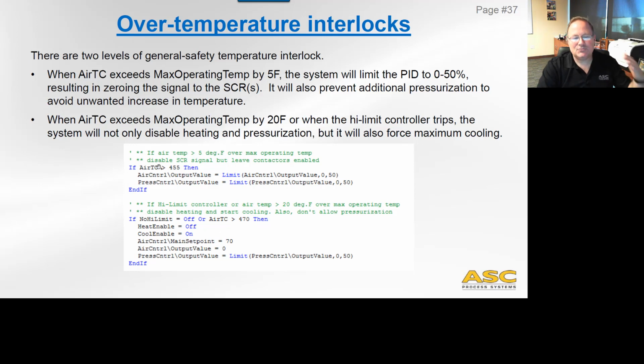And we're taking those two different steps here. One is when the air temperature just goes a little bit above, we're just going to limit air control and pressure control to no more than 50%. What that does is stop heating and stop pressurization, and hopefully that's just a little overshoot that's occurred, and we don't want to take drastic action like dropping contactors and doing this other stuff. So this is a preliminary limiter that is going to limit the SCRs and the heaters, but it isn't going to take drastic action, okay? Drastic action, though, occurs when air temperature gets more than 20 degrees above or the high limit is engaged.